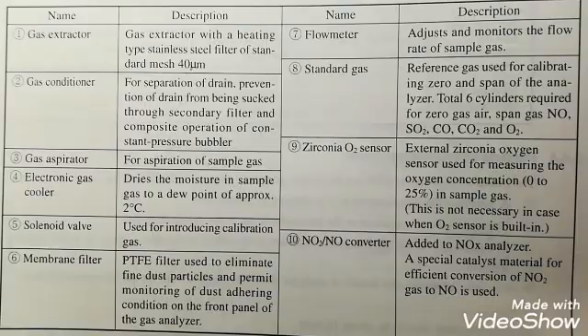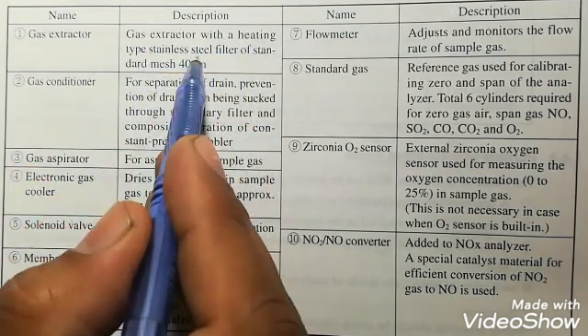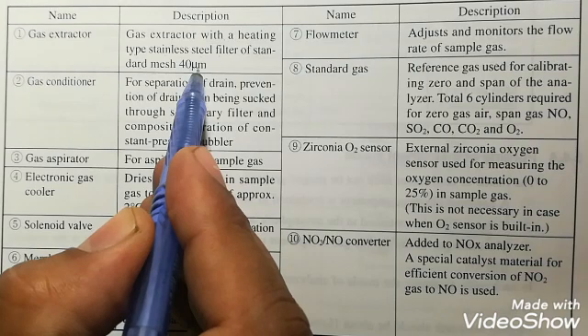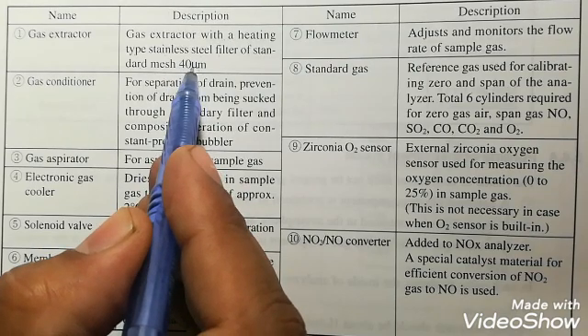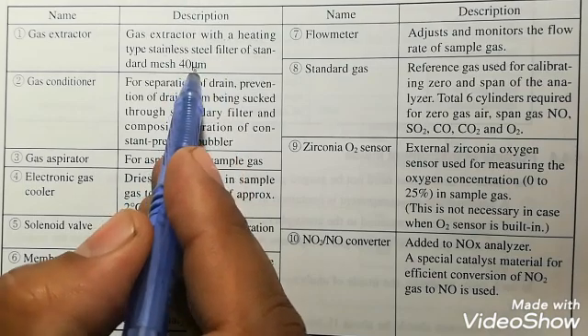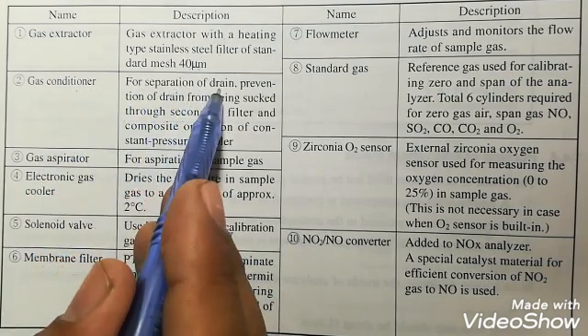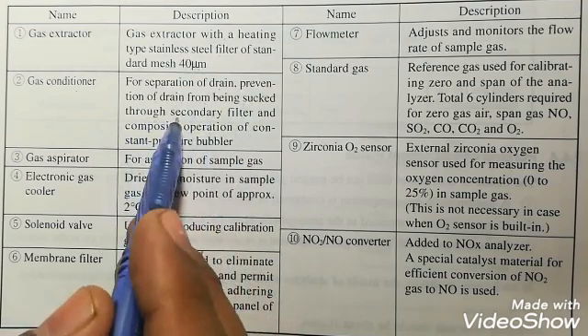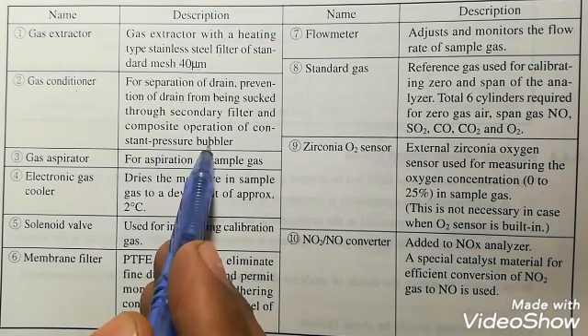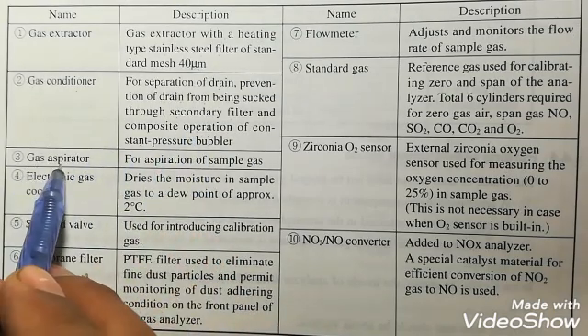So now I will tell you what are the main purposes of all these components. As you can see, this is the gas extractor with a heating type stainless steel filter of standard mesh of 40 micrometers, so it will filter out any particle which is up to 40 micrometers. This is the function of the gas extractor: it has a heater and a filter. The gas conditioner is for separation of drain and prevention of drain from being sucked through secondary filter and composite operation of constant pressure bubbler.